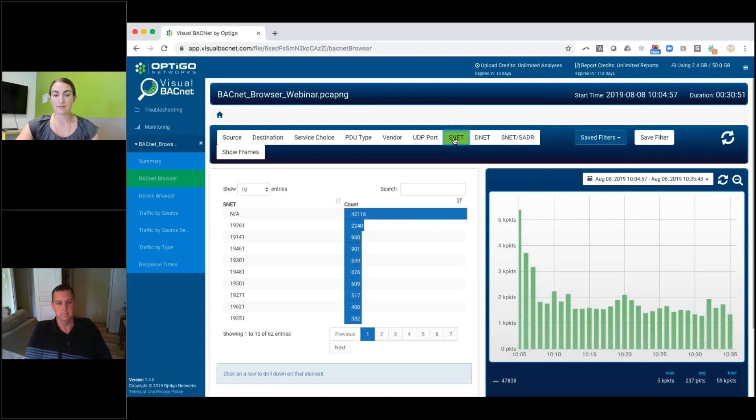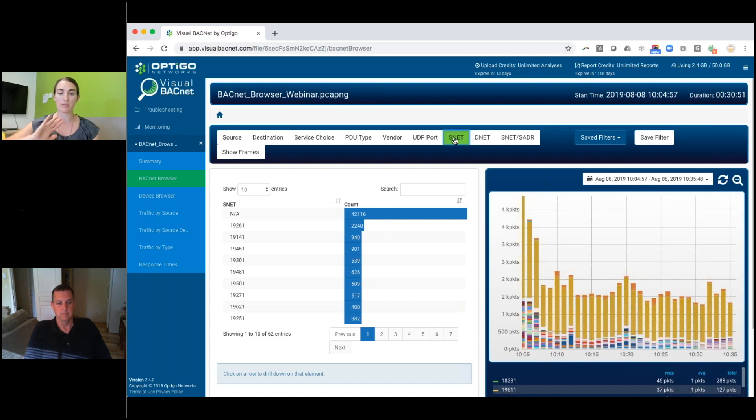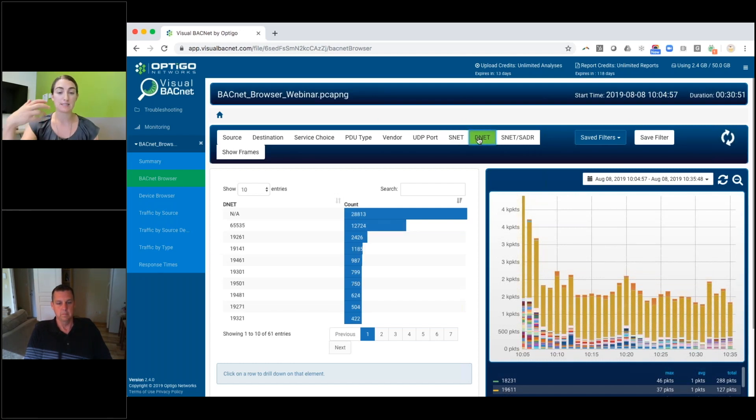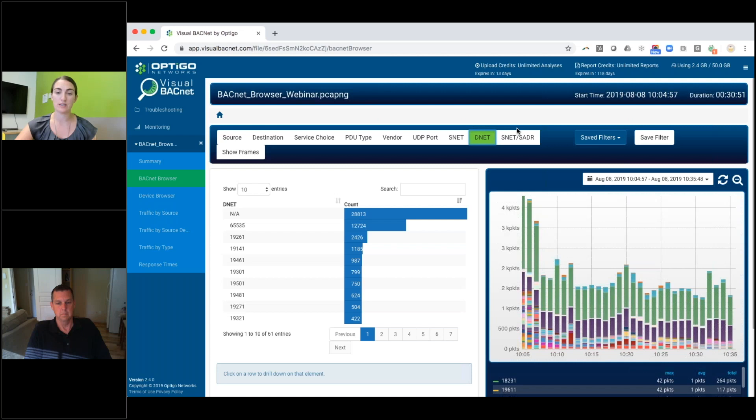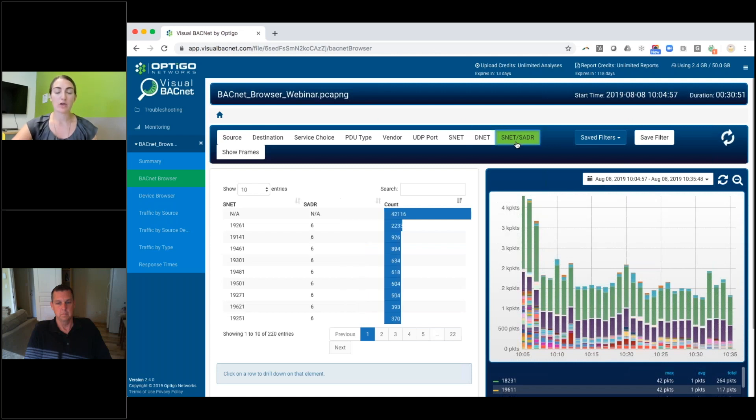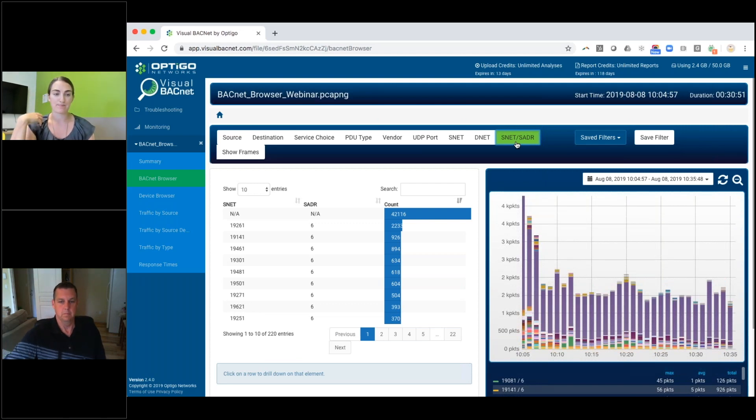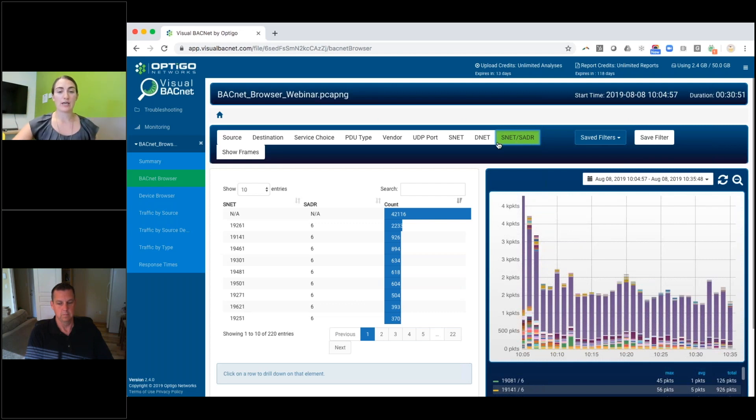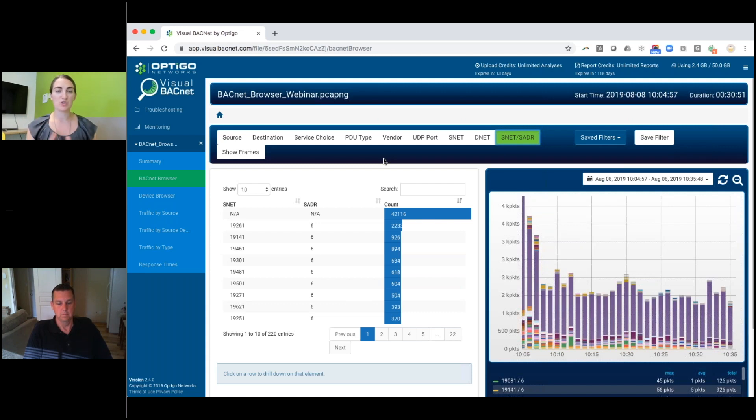All of these last three are similar. So this is showing you the source network. So the network that the packet was sent from, as well as the Dnet or the destination network. So what network is it being sent to? And you'll notice that when I click this, this graph updates accordingly. And the combination of the source network and source address, which should be a unique combination with every device on your site. So that's all of the different things you can look at. But the power of the BACnet browser is really in the ability to put multiple filters on top of each other.